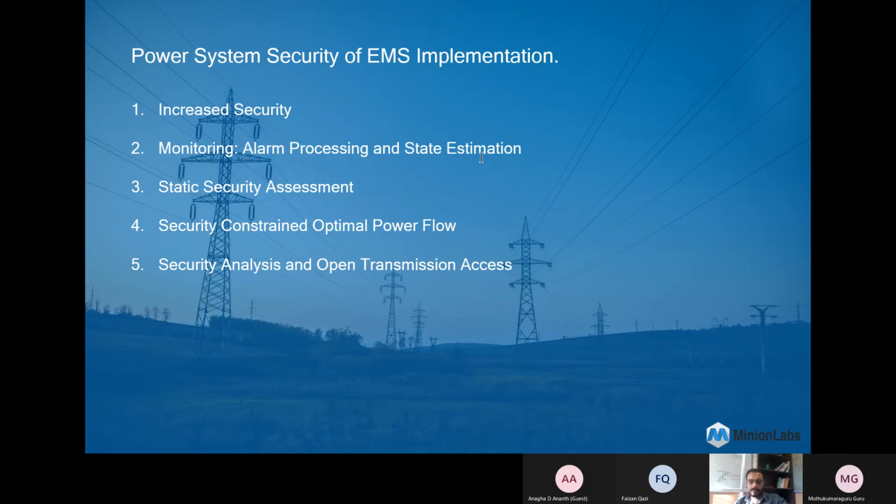The modern EMS combines supervisory control and data acquisition, that is SCADA capabilities, along with the generation dispatch, scheduling and control capabilities. So the modern EMS now has the ingredients necessary to provide operators with advanced security analysis capabilities. This feature is considered absolutely necessary in operating a power system, as it allows operating personnel to make the most efficient use of the transmission system by loading it up to its limit without placing it in any insecure state.